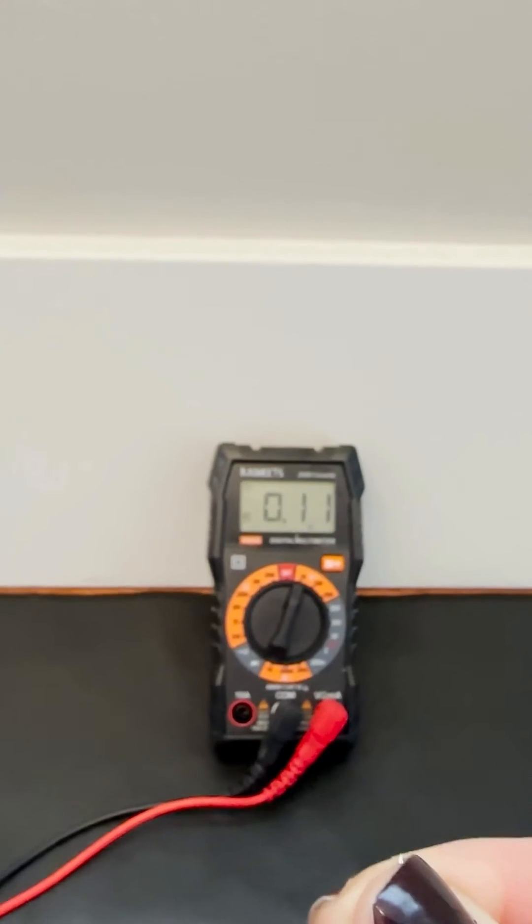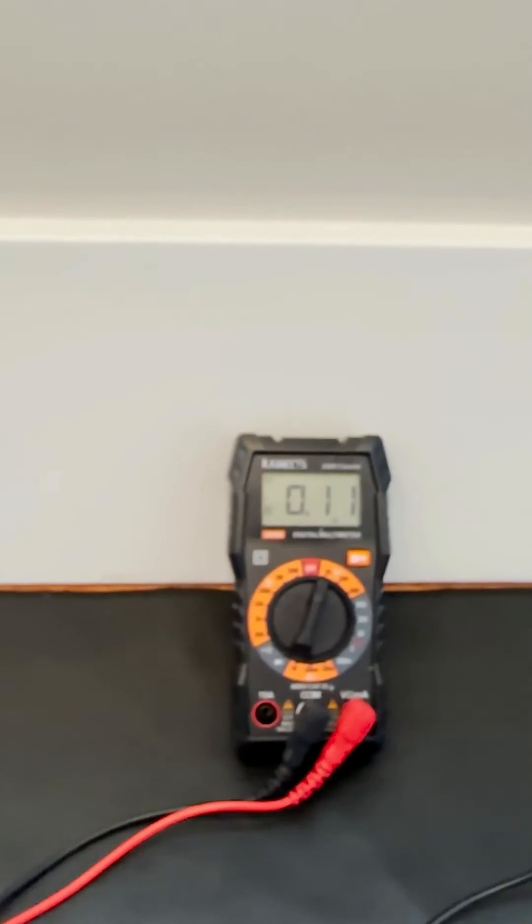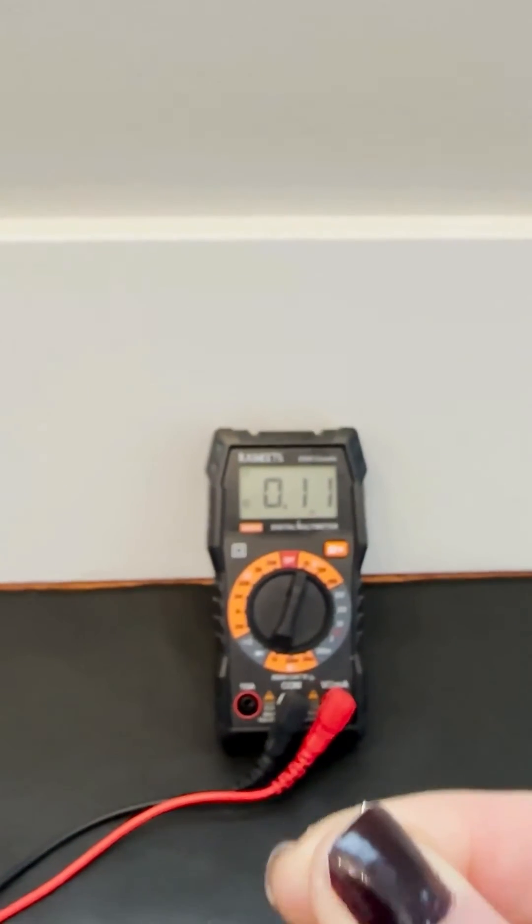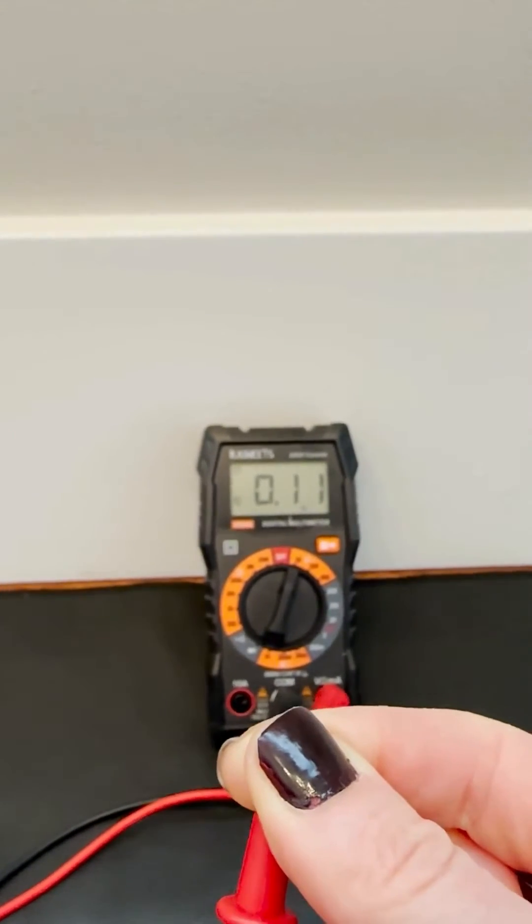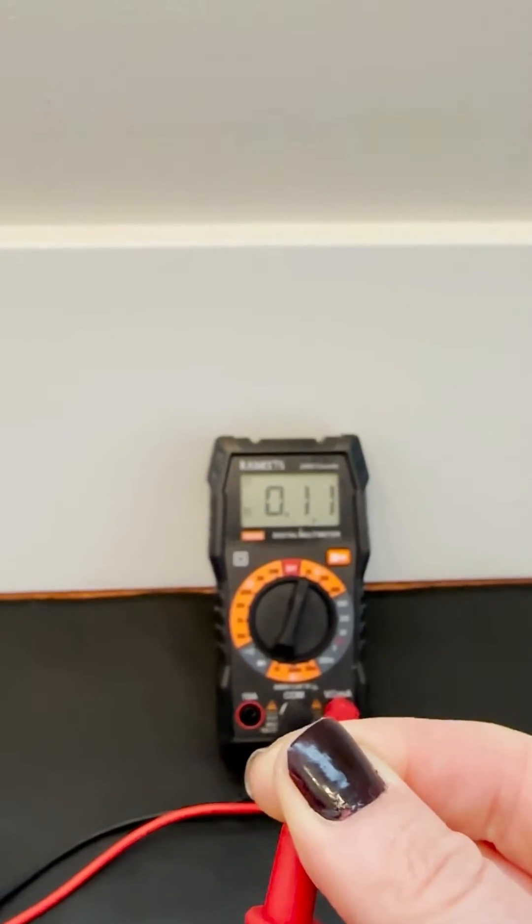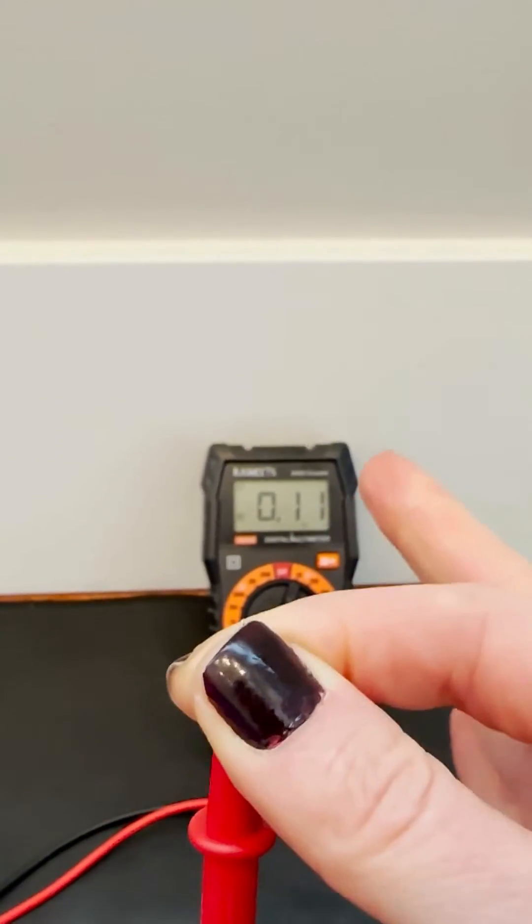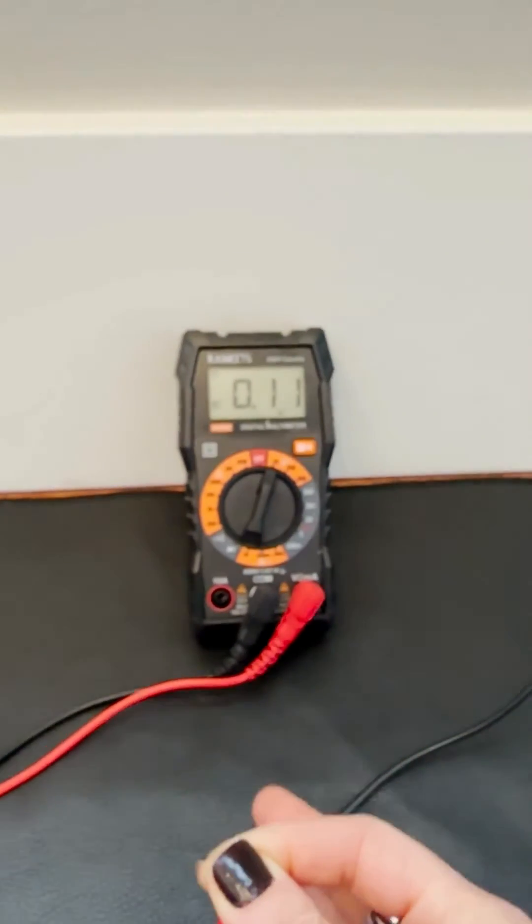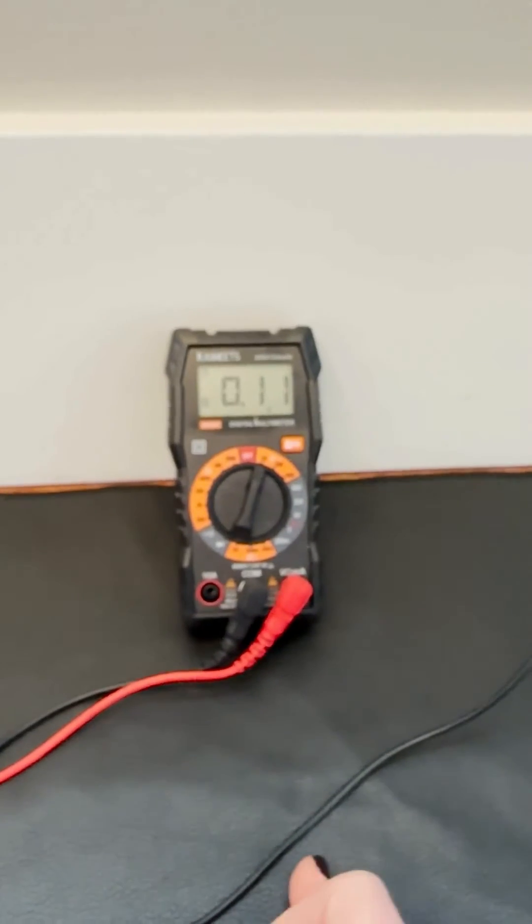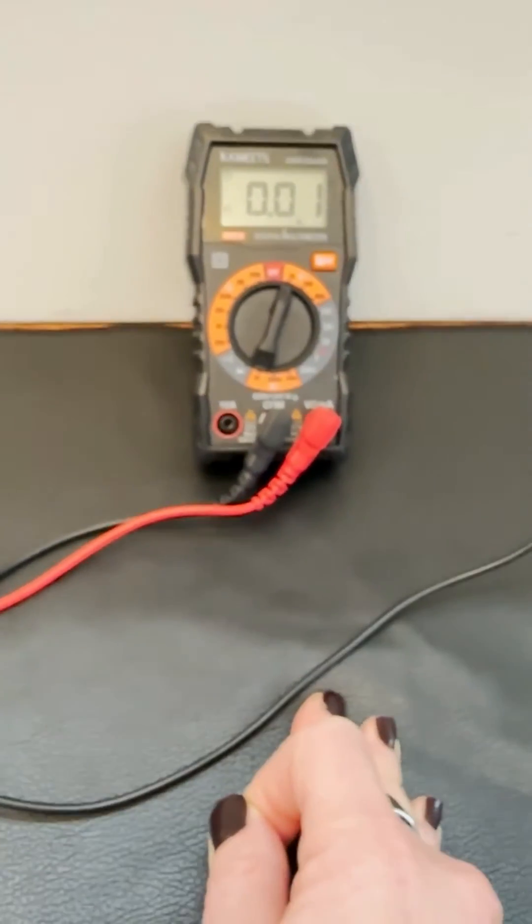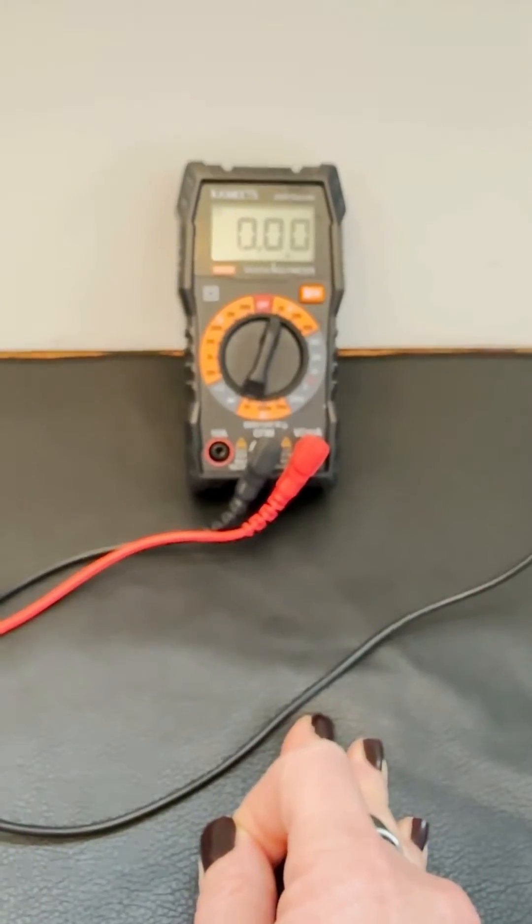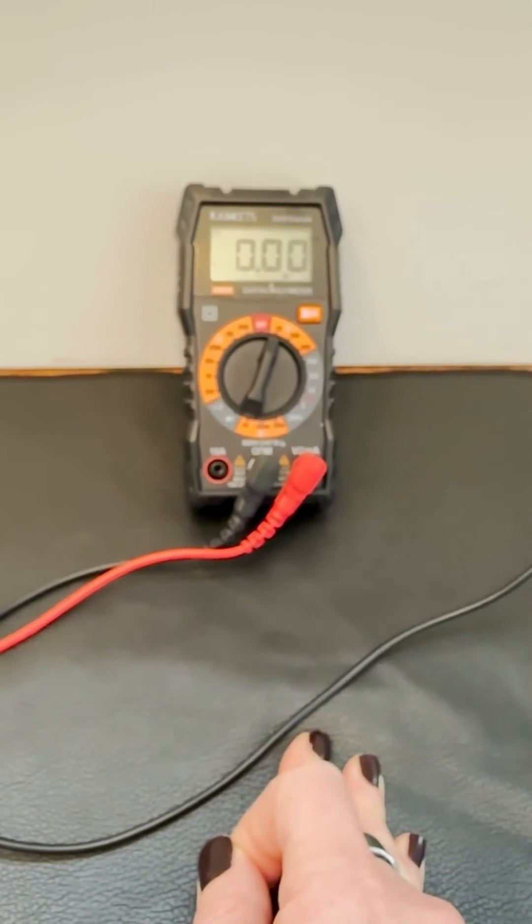I have about 0.11 volts right now running across my body. What I'm going to do is, with the probe in my hand, I'm just going to take my hand and touch it to the mat. I still have the probe in the hand, and you will see that it goes to zero. So we know that our grounding mat is grounding us.